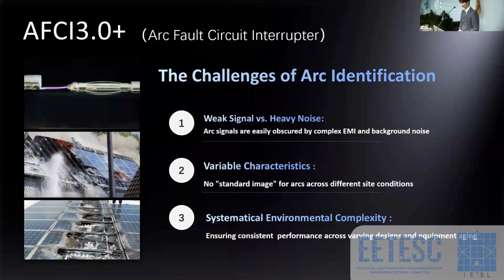So the risk is clear, but how to identify a real arc rather than a fake one? That's the point. I make a list here. You can find that from this slide. There are 3 challenges of arc fault identification. First one is the weak signal versus the heavy noise, because the arc fault signal is really tiny. It's easily buried by the noise. The second is the variable characteristic, because for the arc fault, there was no standard image. It always changed. And the third one may be the most challenging, because currently the PV plant is larger than ever before. As I said, there are more than thousands of connection points, which makes it a huge challenge.